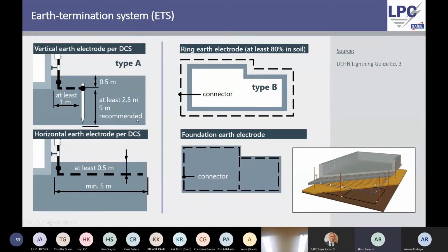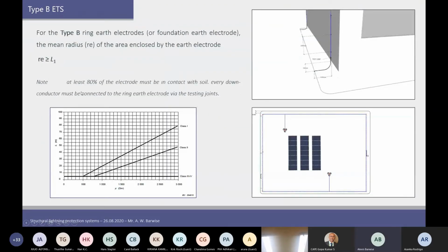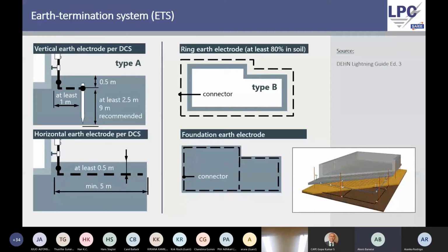What is important on type B systems, which I failed to mention, is that if you are using ring earth electrodes, at least 80% of the ring itself, so of the conductive part you're using, either steel or copper, whatever it might be, has to touch earth itself. It has to touch the soil. Otherwise, obviously, it's not doing the part of dispersing or distributing the currents to earth itself.